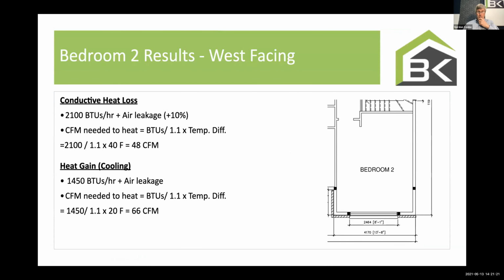Okay, so we're back to this room and thinking about bedroom number 2. My apologies for being out of order. But thinking about how do I make sure I get that 48 and 66? And you might say, well, I could put 2 ducts into that room and close one off in the summer, close one off in the winter. Sure. Fundamentally, I need to be able to balance the house. Bedroom number 3 has the same size duct, same square footage. I need to be able to say to the homeowner, or when I first build the house, this one's facing west, I need more air.